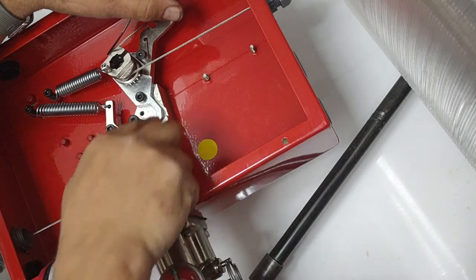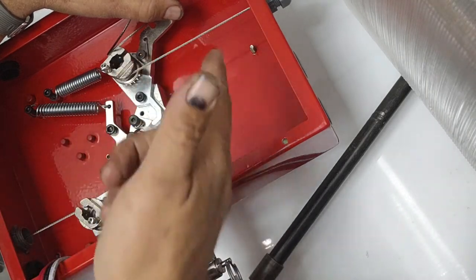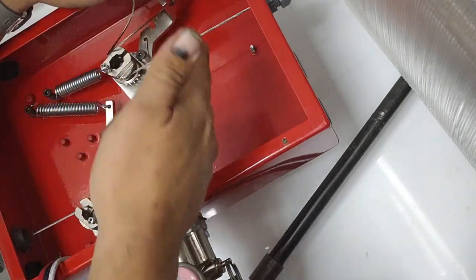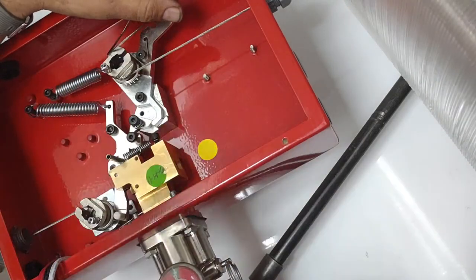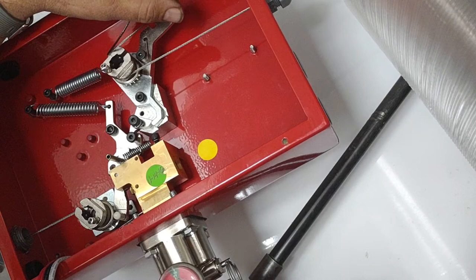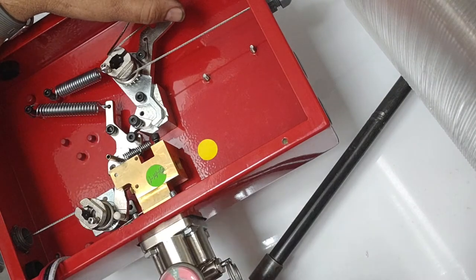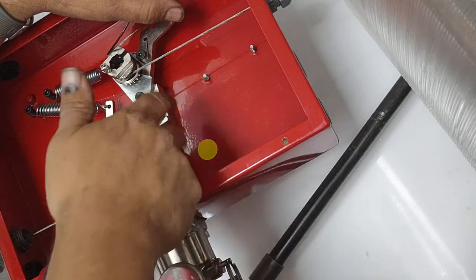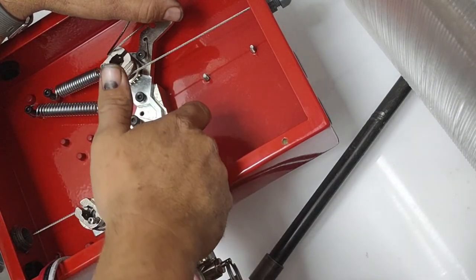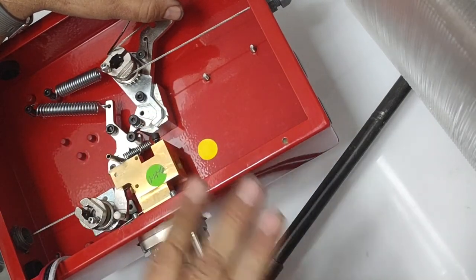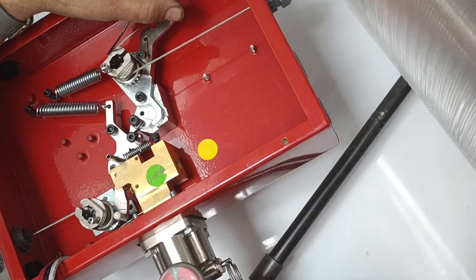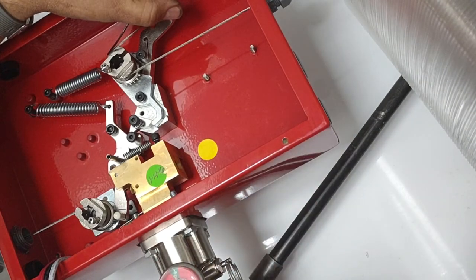I'm going to manually set this off to show you what happens when it goes off. Notice right here it's got a little clip holding a little pin that swivels here, that holds this open and this open. When this moves, I'm going to push it up like we're doing the pull station. It's going to set the system off, but I don't have the cartridge in so it's not going to release what's in the tank.